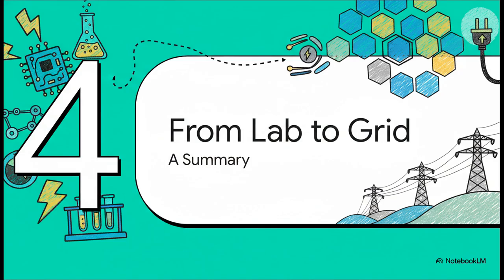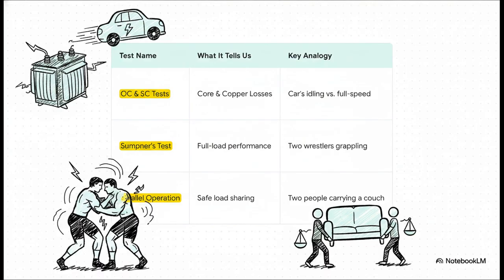All right, let's pull all this together and recap the whole journey. From a standalone unit in the lab to a certified piece of hardware that's ready for the national grid. We started with the OC and SC tests to get the transformer's DNA. That was our car efficiency check. Then we used the super clever Sumpner's test, our 2 wrestlers, to check full load performance and temperature rise without wasting a ton of energy. And finally, we verified the conditions for parallel operation, making sure our couch carriers can work together safely.